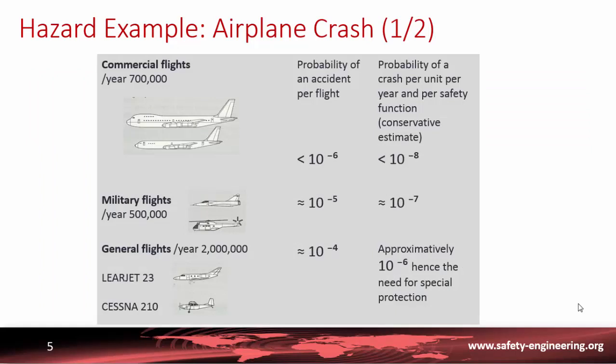We have seen an internal hazard: fire. Now let's look at an external hazard: the plane crash. Through statistics from the aeronautic industry, we can distinguish three kinds of flights. For commercial flights, there are several hundreds of thousands per year, and the probability of accident per flight is on the order of 10^-6. Combined with the probability of the crash reaching a safety function, the result is on the order of 10^-8 per year per safety function, which is sufficiently low to disregard this kind of accident.